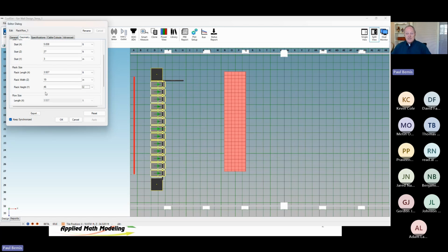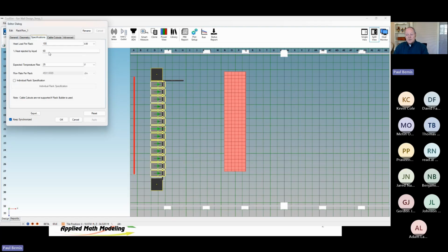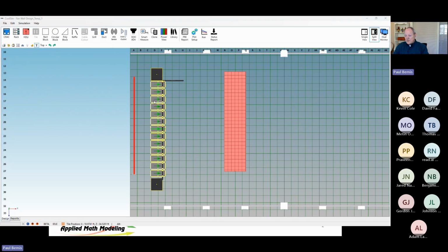Each slot is, I think, 3.75. I can't remember. Well, it doesn't matter. But you've got 46 slots. Okay. So that's that, and by the way, I've got this thing set right now at, in this case, 100 kW per rack, which is where we're headed, but we're dumping 60% of that to water. All right. So these are operating at a net 40 kW of air. So I've got that set up, and I feel pretty good about that.